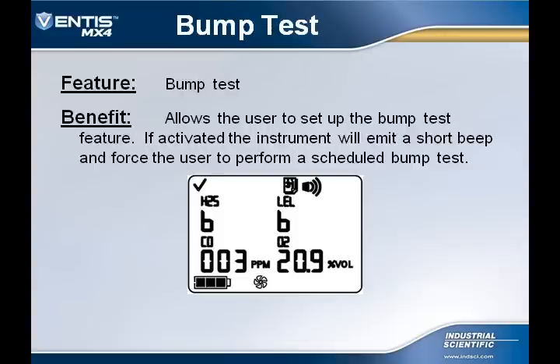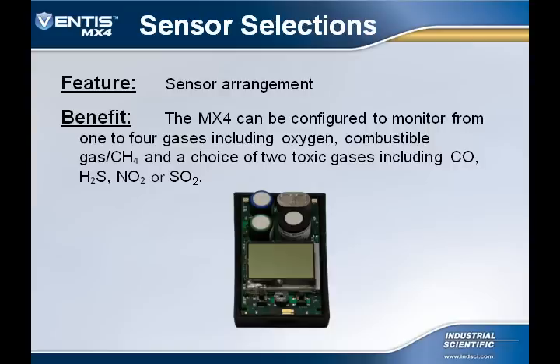This instrument has a user-configurable bump test feature. If this is activated and the instrument is overdue for a bump test, the instrument will emit a short beep and force the user to perform a scheduled bump test. The Ventis MX4 can be easily configured to be a 1 to 4 gas monitor, with gas options of oxygen, combustible gas, including methane, carbon monoxide, hydrogen sulfide, nitrogen dioxide, and sulfur dioxide.